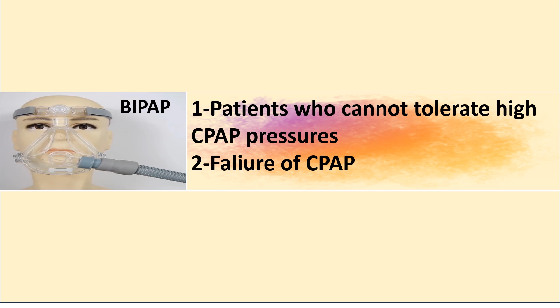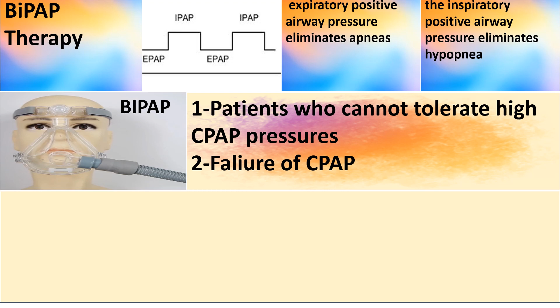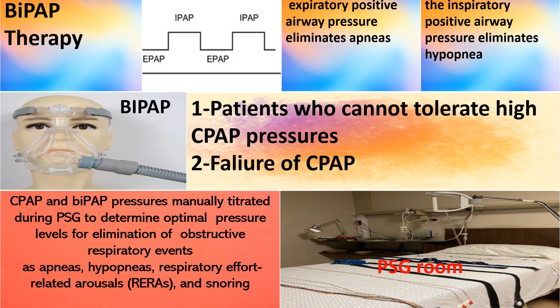BiPAP generally used when patient cannot tolerate high CPAP pressures or in cases of failure of CPAP therapy. BiPAP delivers two different pressures during respiratory cycle. High inspiratory pressure, IPAP, to eliminate hypopneas, and lower expiratory pressure, EPAP, to eliminate apneas. CPAP and BiPAP pressures are manually titrated during polysomnography to determine the optimal pressure levels for elimination of obstructive respiratory events as apneas, hypopneas, respiratory effort-related arousals, and snoring.